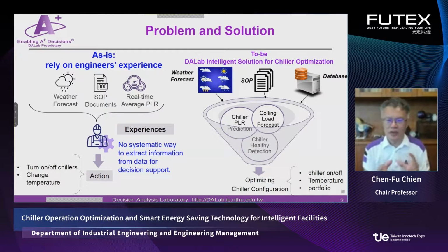Using our technology, on one hand we use big data to forecast the weather and tool performance, and we consider all those decision rules into our system. We also collect data based on sensors from the production environment and the machines, so we have a solution with different modules, including cooling load forecast for the cooling load demand, as well as the supply from the chiller. They have different performance profiles and even different tool health conditions. When we have an alternative combination of chillers, how can we optimize the configuration? How can we deal with the change of temperature and production needs along the time? All of this is optimized in our intelligent solution.